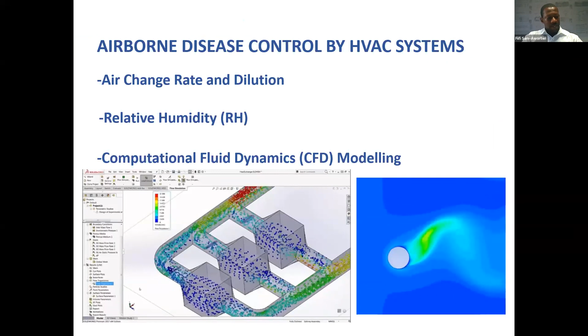Going one step further into the science of the HVAC design of this facility, I'll briefly talk about air change rate and dilution, relative humidity, and computational fluid dynamics, that's CFD modeling. So air change rate per hour is basically the time it takes to completely replace the air in a room with new air in 1 hour. Complete change of air in a room would also mean complete dilution. Time to provide 99% dilution.